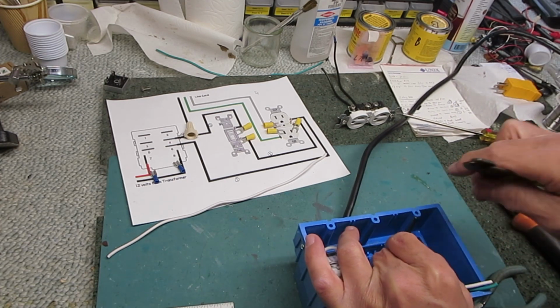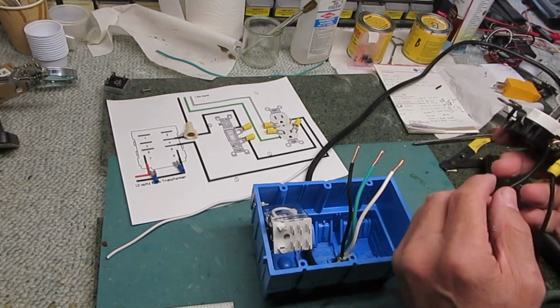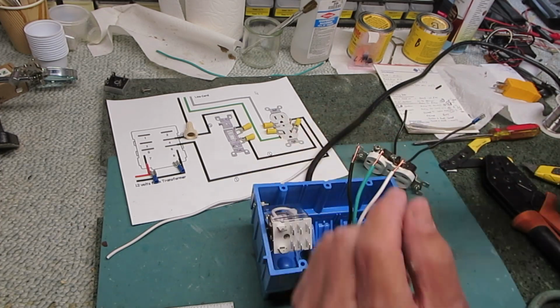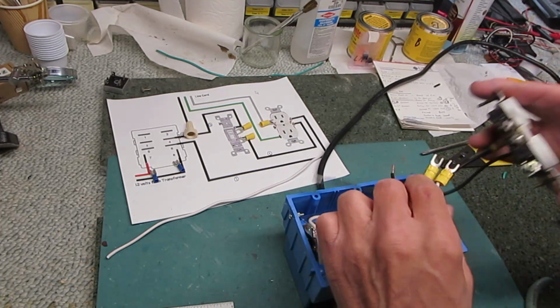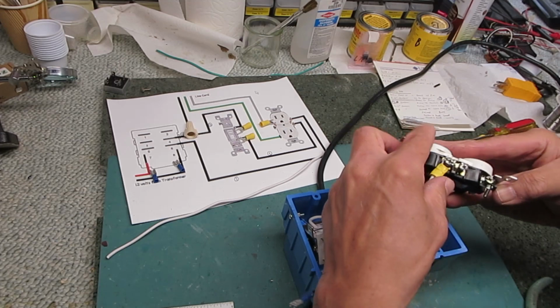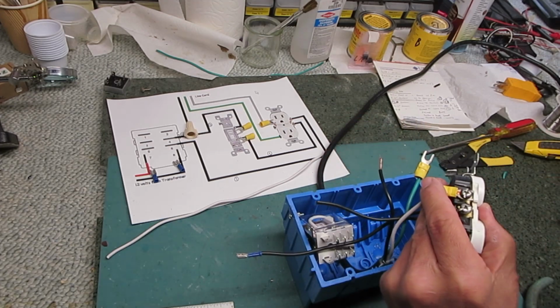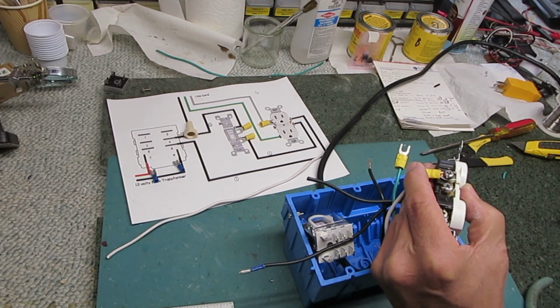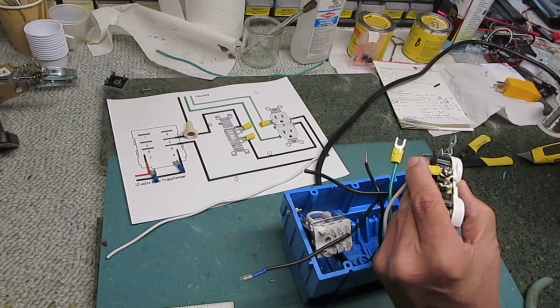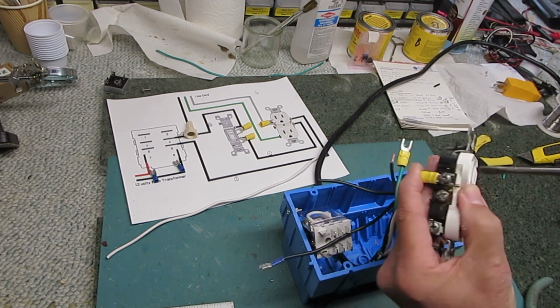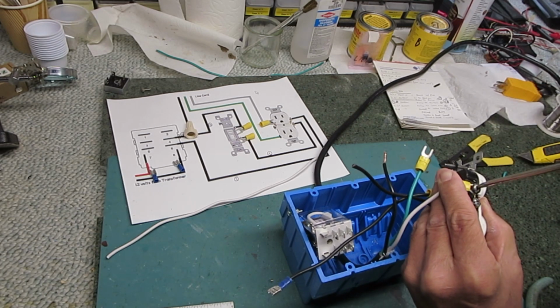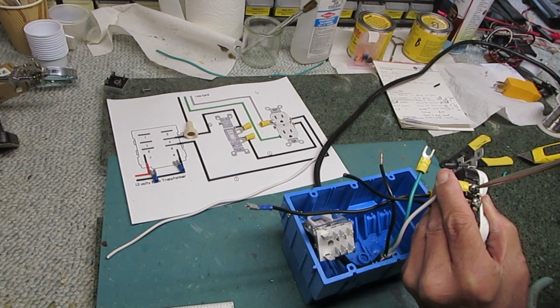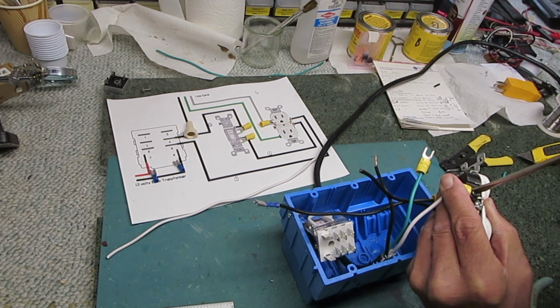Strip all the wires. Okay, I've got those stripped, and now I'm going to put on the connectors. Connectors are on. Put the white under the screw on the same side as the ground—it's also the side with the longer slot, either screw—and that'll make the neutral connection.